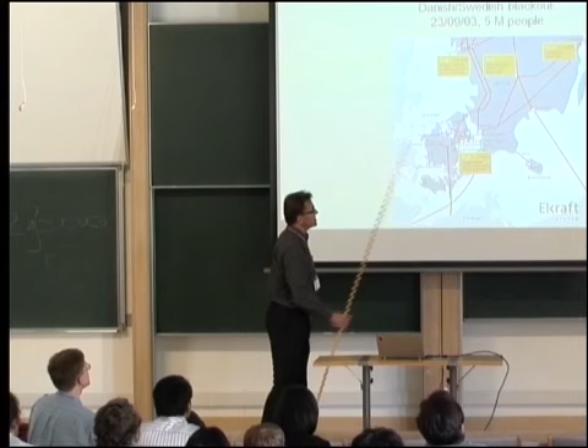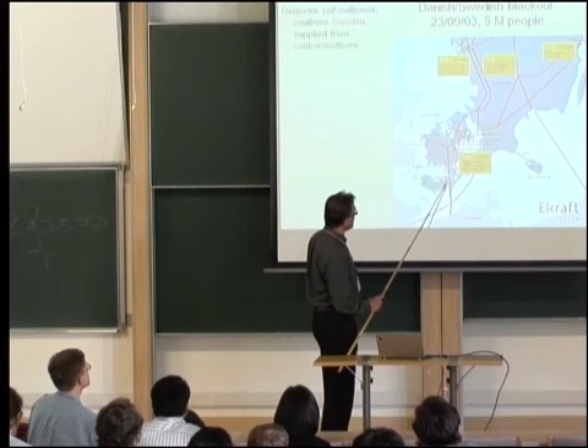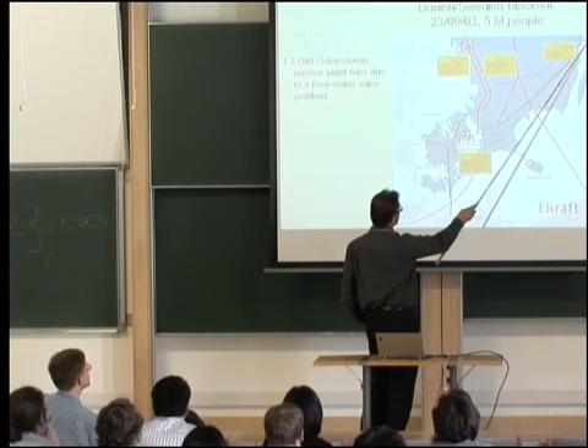The situation was normal load with a big margin, nothing should have happened really. Denmark is self-sufficient, but the southern part of Sweden is supplied by big power stations located in the north, so power is flowing down those transmission lines. Then that power plant tripped due to some internal problems, so we lost one large power station - okay, N-1 contingency, no problem.